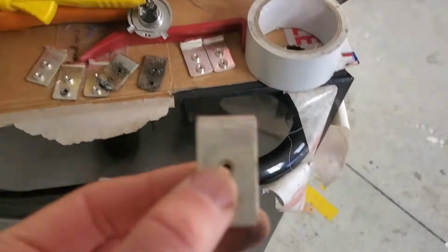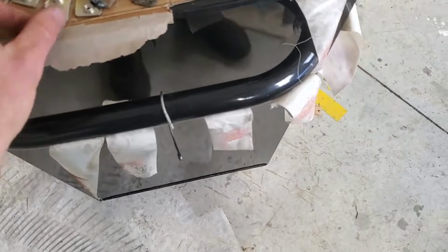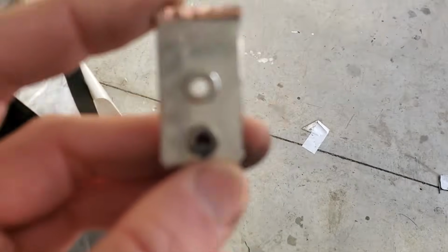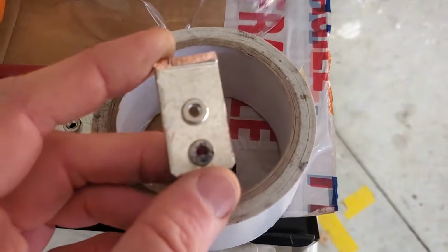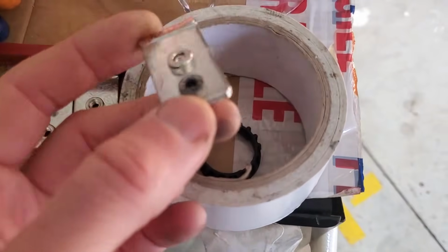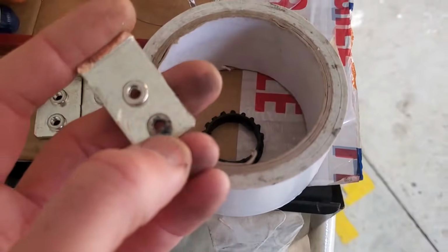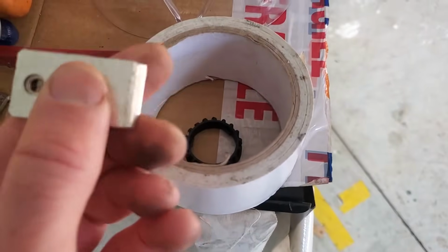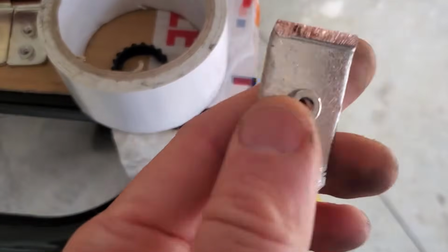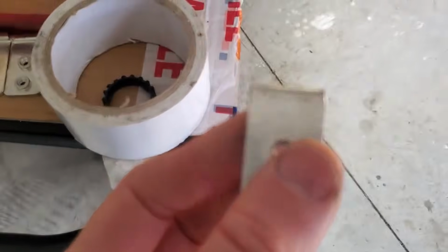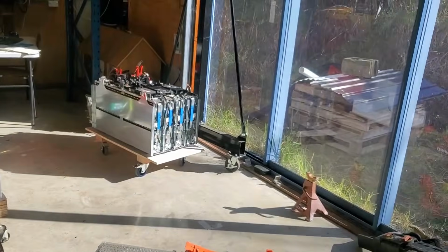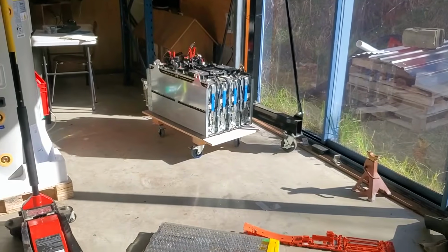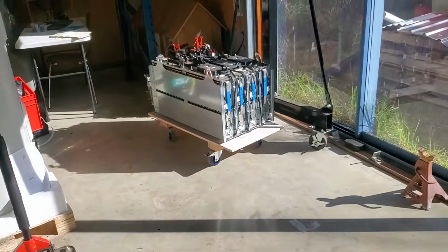Anyhow, one of those was touching the case. And there it is. It actually touched, and there had been some kind of another connection at another point, and it's welded itself to the case. Now that's fine, because that doesn't immediately cause a problem. But then the next one that does that, you've got a big ass short circuit on a big, high current delivering battery, and it's totally predictable.